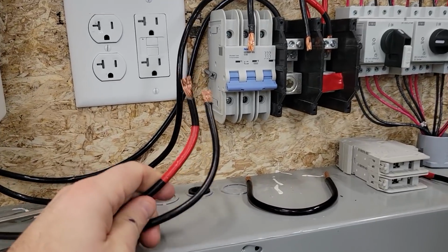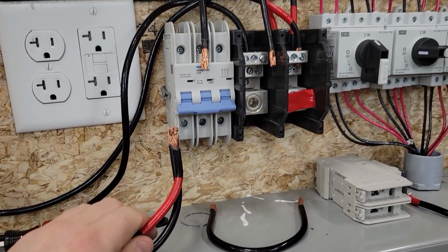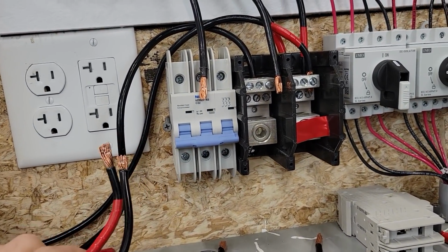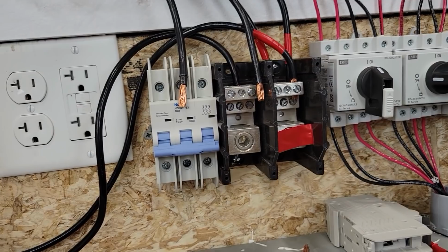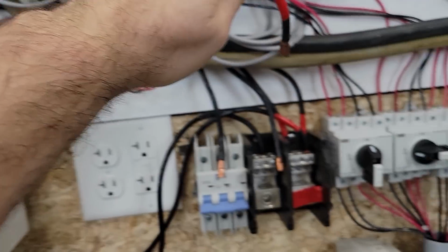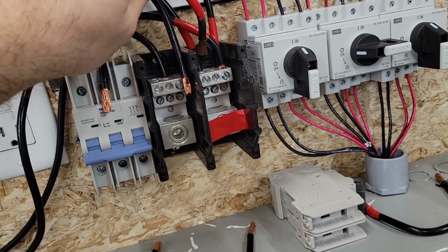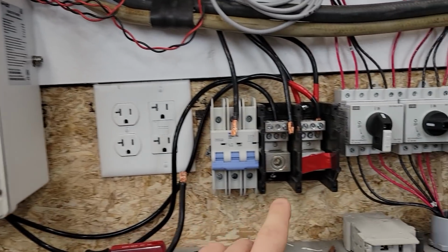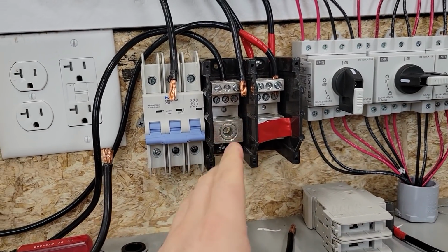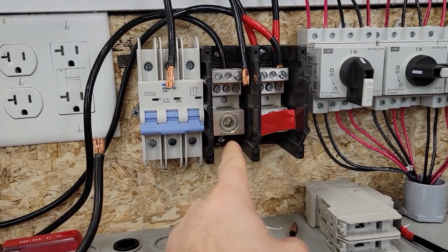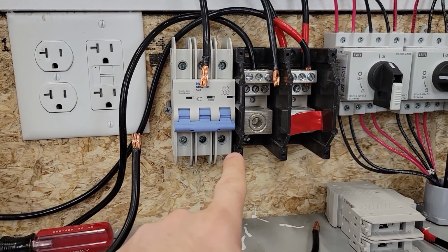So what I'm going to do is take these out, and I need to put them in their right spot. So for the reds, the L2, this is just going to move up, and I'll drop it in the top. Now the black one feeding to the panel is going to go directly off the terminal block. But in order to feed this particular block, it's going to be fed with the two poles.